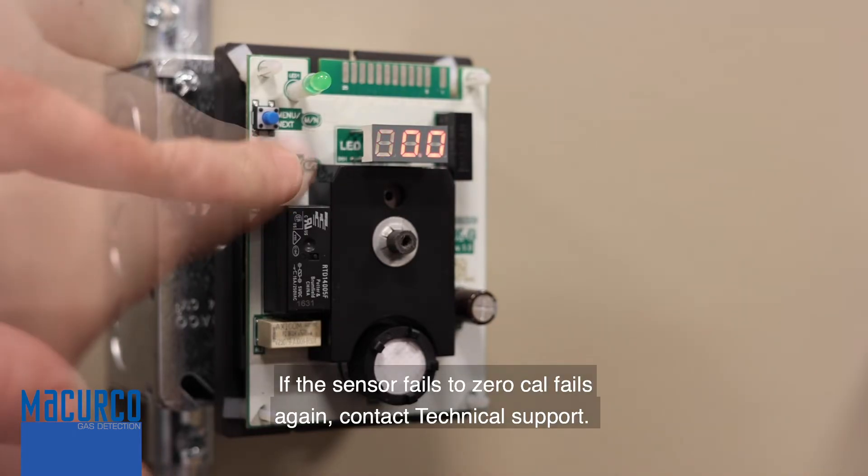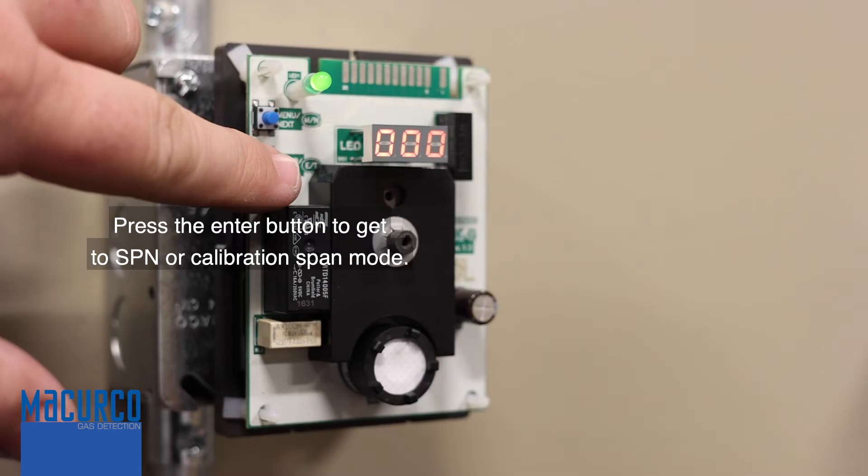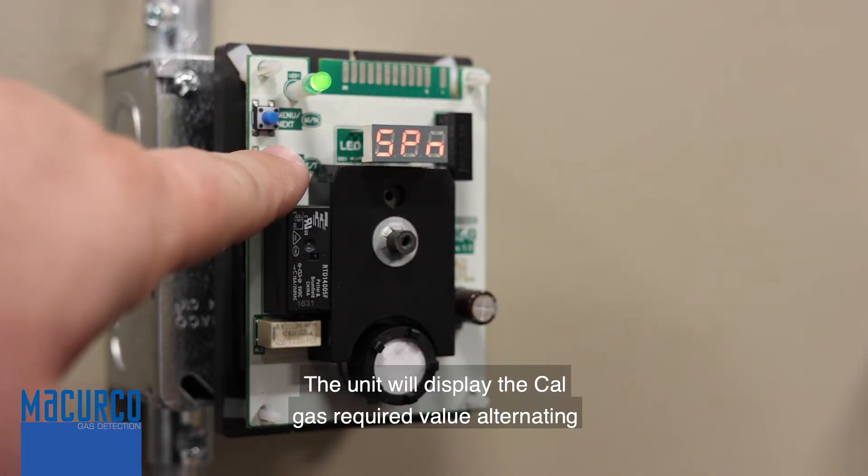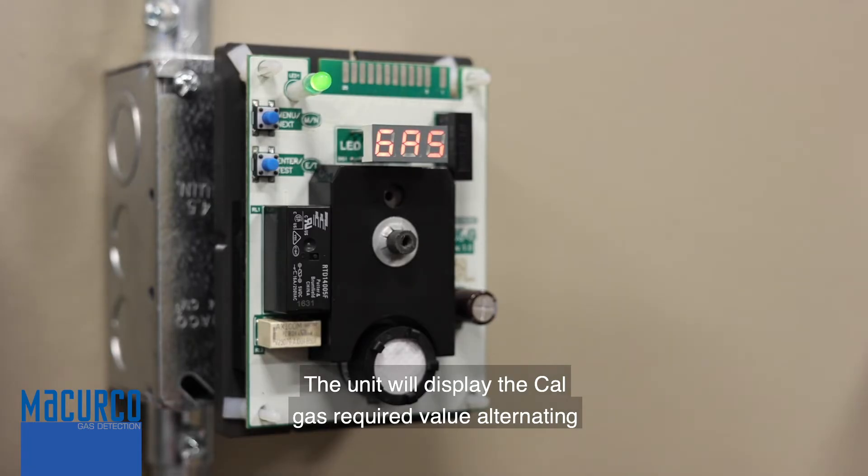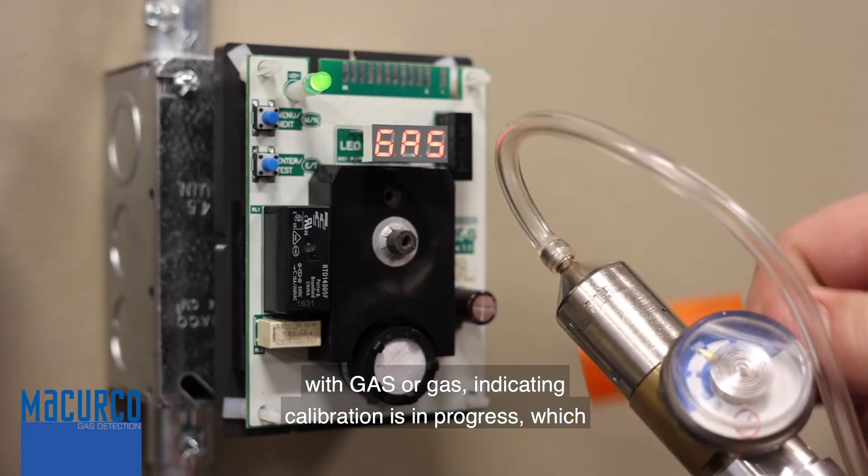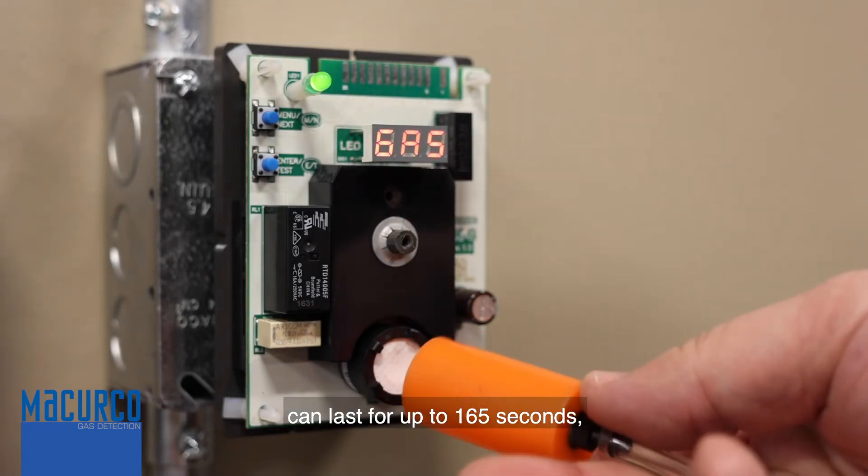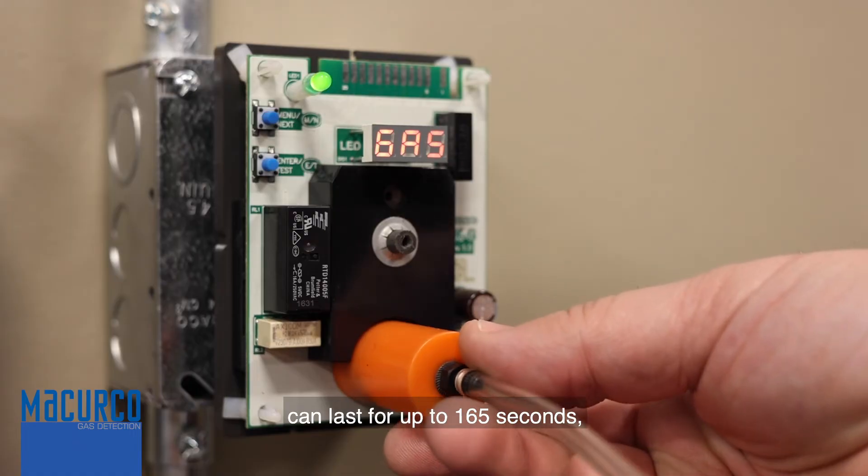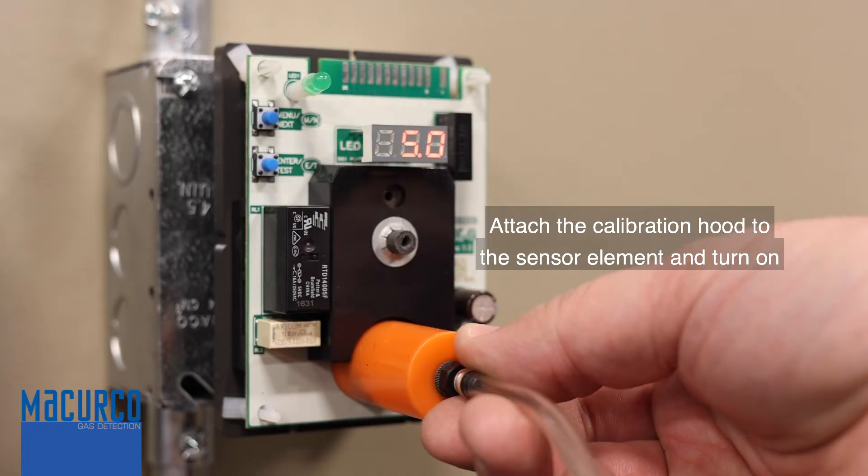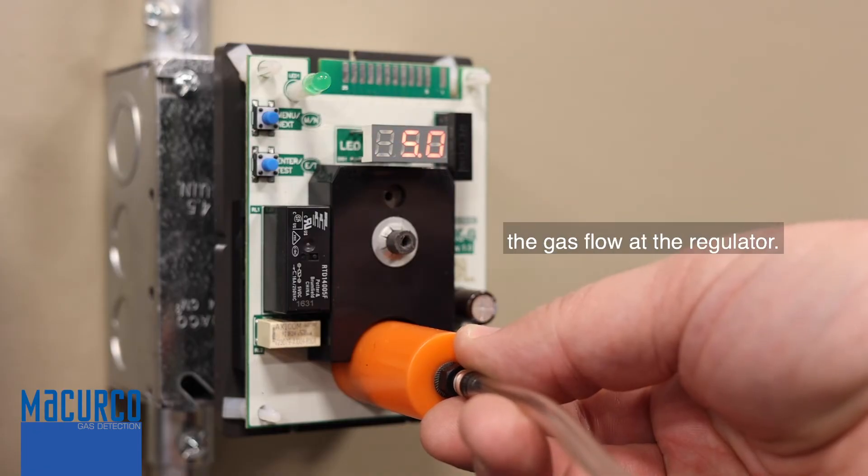Press the enter button to get to spn or calibration span mode. The unit will display the cal gas required value alternating with gas, indicating calibration is in progress, which can last for up to 165 seconds. Attach the calibration hood to the sensor element and turn on the gas flow at the regulator.